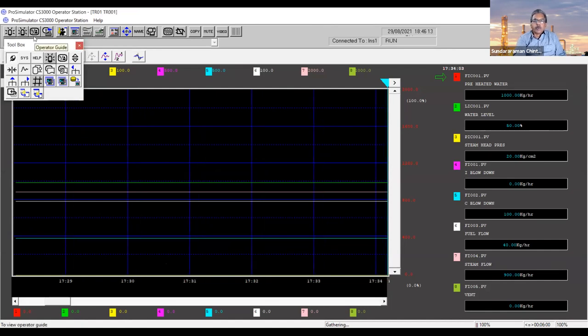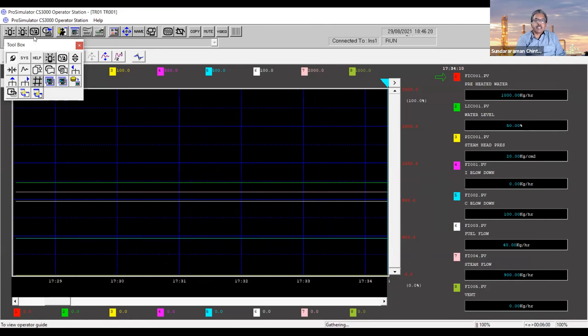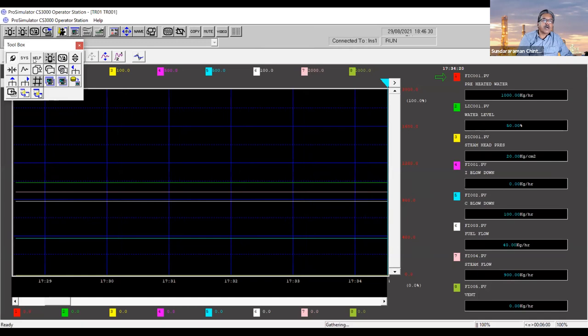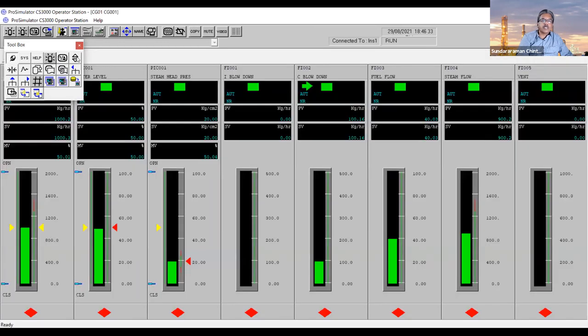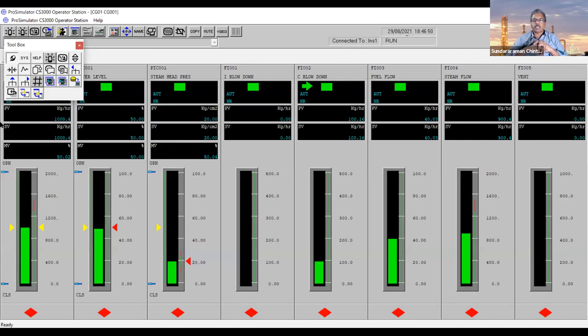Let me run the simulation model for a few more minutes. The plant was previously under static condition; as it runs, we will return to this page. We also have an alarm page — right now there are no alarms — and a control group page where different instruments are grouped for operational convenience. I want to show what happens when making an adjustment to a single control, since all are interlinked. When I increase throughput by 5% by adjusting the raw material flow control, the level in a particular vessel will go up, and accordingly the level valve will open more flow to the secondary vessel.